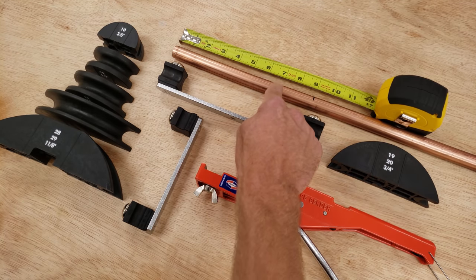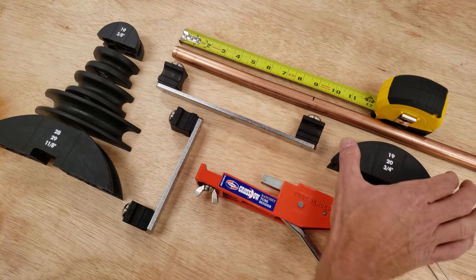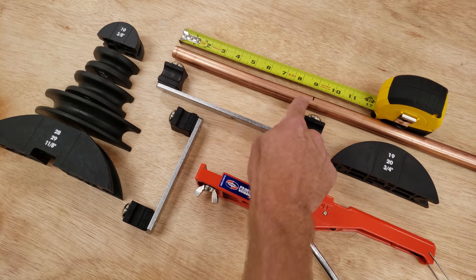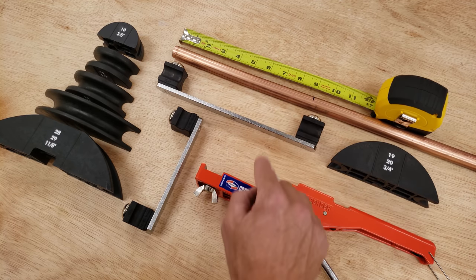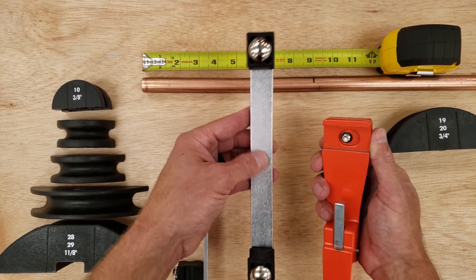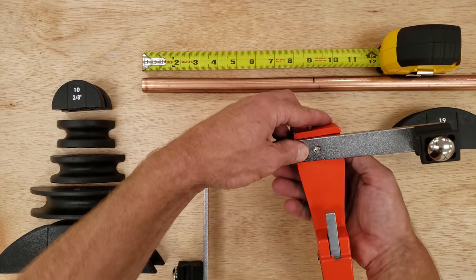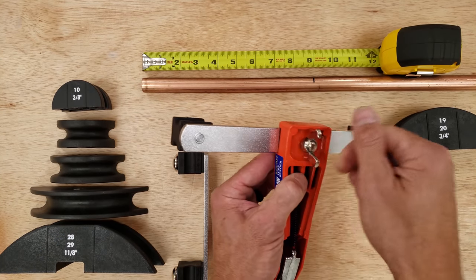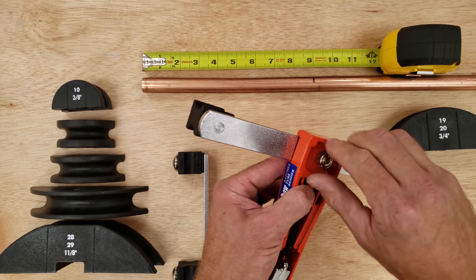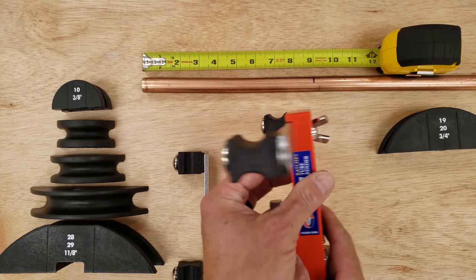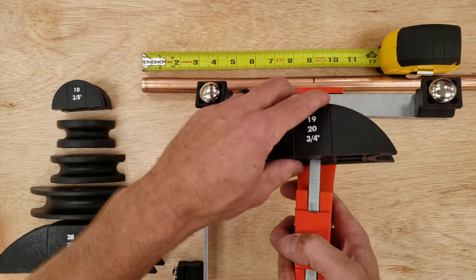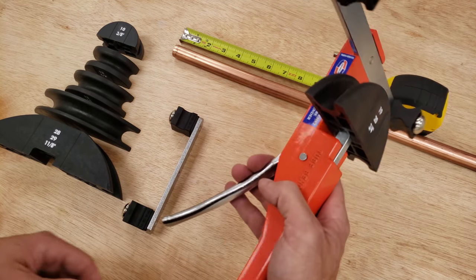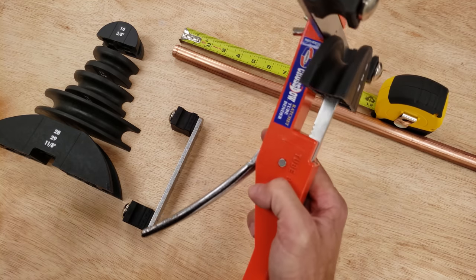In this case we have three-quarter OD, and so we're going to select a three-quarter mandrel and a three-quarter cross section. We already have our tube marked. In order to put your crossmember in, you just place it right over the bolt and then tighten the wing nut. Put your mandrel in, and then you see this ratcheting, and then there's a release.